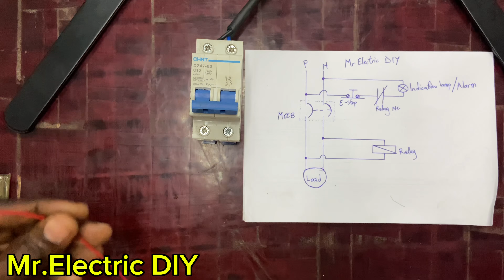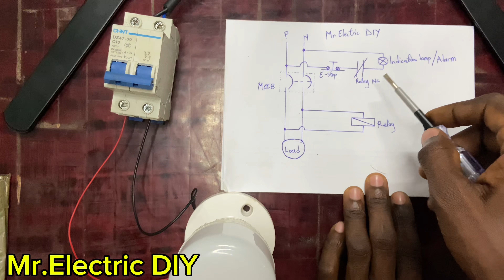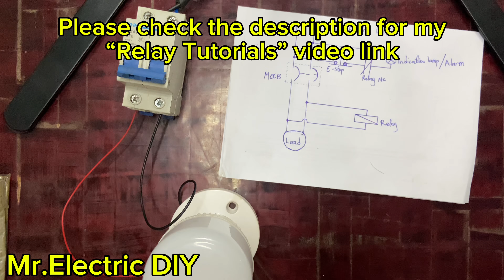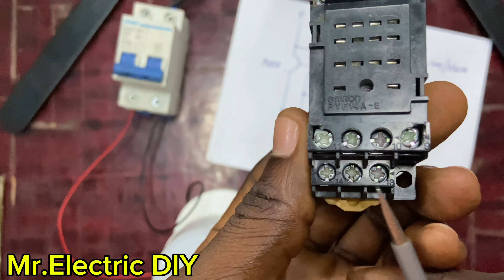I have the lamp here. Now I've connected my load. I have the load here. I've connected it. And in order for me to use the normally closed contacts on the relay, I have to connect this relay over here from the downside of the circuit breaker to the relay, the power terminals. 13 over here is the live and 14 here is the neutral. That's the A1 and the A2.